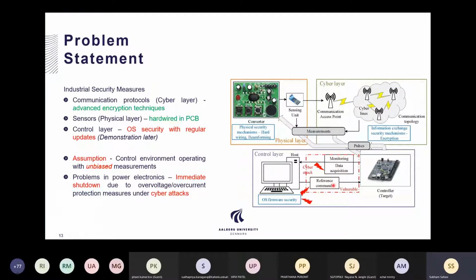Let's say you've given a command to operate this power electronic converter at 50 Hertz, so you give a command on the frequency reference to 50 Hertz. But if I am remotely accessing this platform, I can change this reference value from 50 to 55 Hertz. Because you are in an interconnected system, that can create synchronization issues and you will be tripped out of the system.